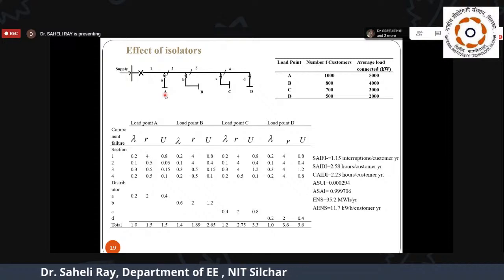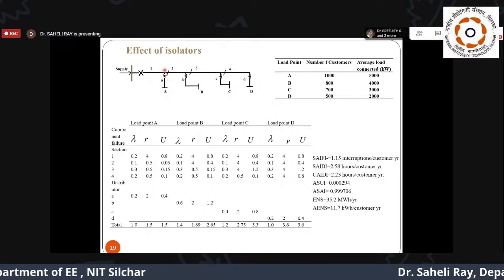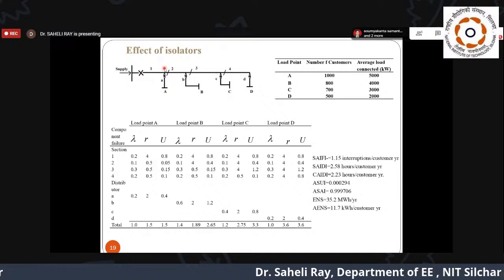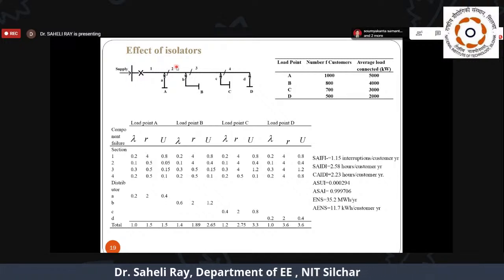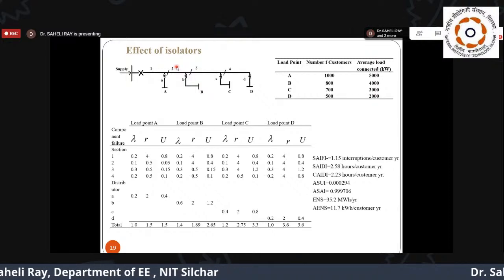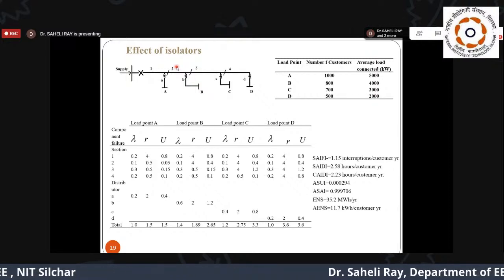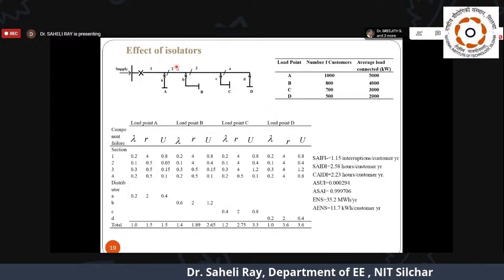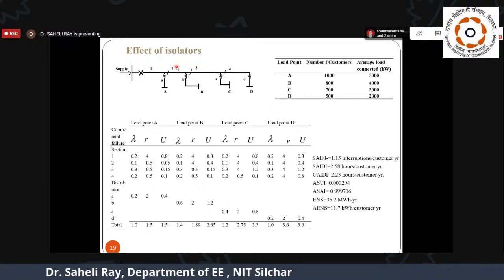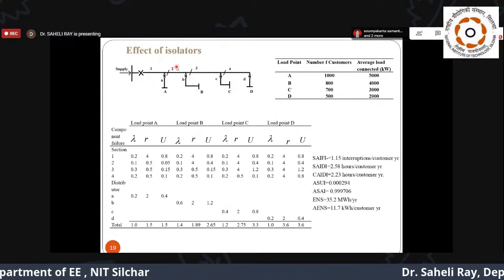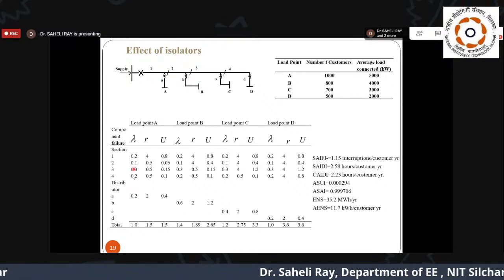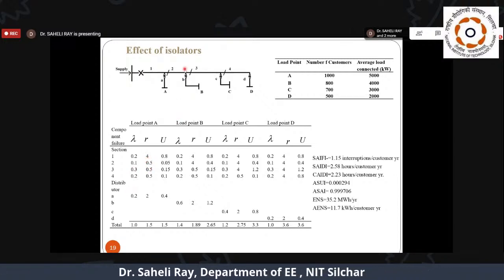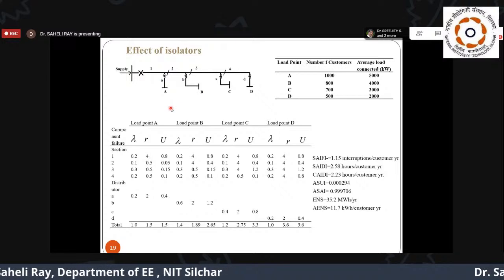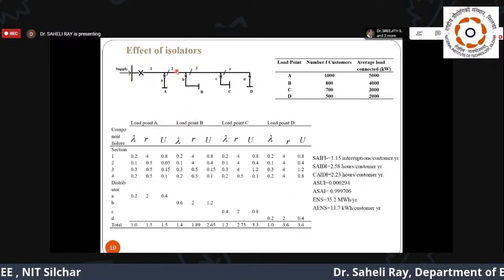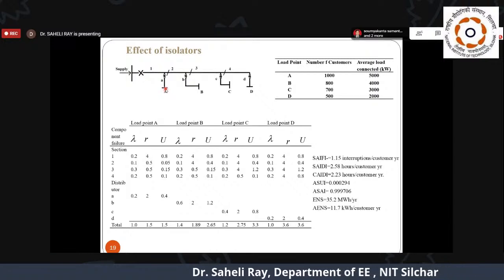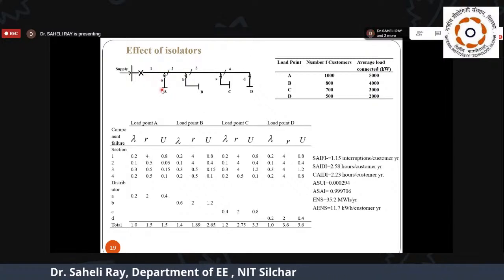Only time required to restore power to point A will be the operating time of the switch. Let us consider here that it is a manual switch and it takes half an hour to operate, because manual switches have several constraints also. You have to identify where the fault is. You have to send the persons to that particular location, and isolate the faults and all. Let's say for this example, the average timing for switch operation is half an hour. So 0.5 we have considered. So obviously the repair time of this segment was 4 hours. Instead of that, we need not wait for 4 hours to restore power to point A, because within half an hour we can isolate this segment and restore power to point A.